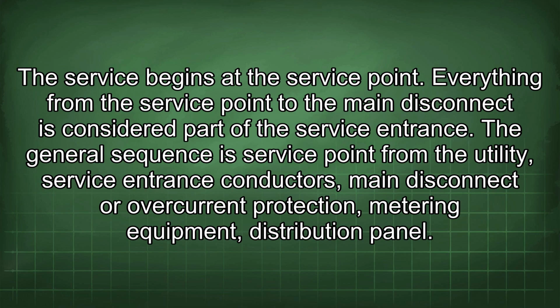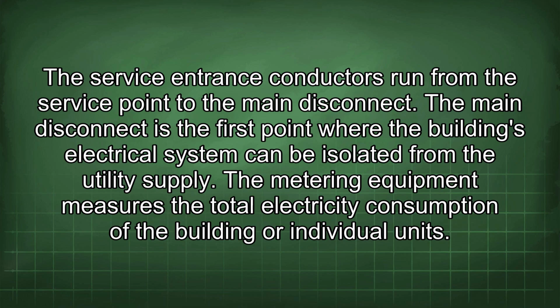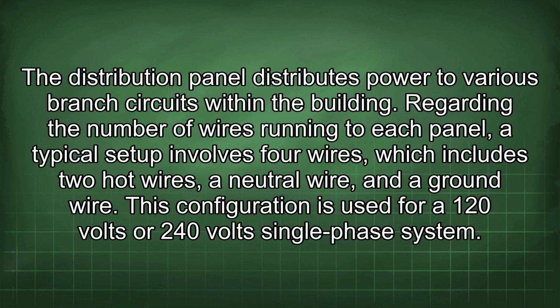The general sequence is service point from the utility, service entrance conductors, main disconnect or overcurrent protection, metering equipment, distribution panel. The service entrance conductors run from the service point to the main disconnect. The main disconnect is the first point where the building's electrical system can be isolated from the utility supply. The metering equipment measures the total electricity consumption of the building or individual units. The distribution panel distributes power to various branch circuits within the building.